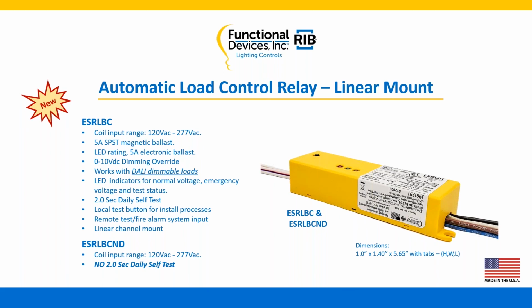things. Something new to us, but primarily what happens in theater settings and so forth, they're using a DALI protocol. So when they're doing that, they need some way to override and make sure fixtures come on to full brightness in case of an evacuation there. LED indicators, as our other products have, and the ERLBC has the 2-second self daily test. Localized test button, as we mentioned. It also has the remote test fire alarm system input.